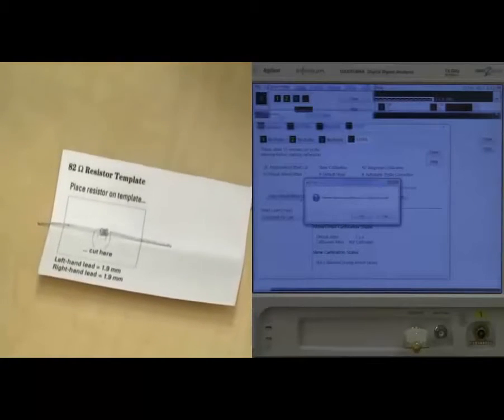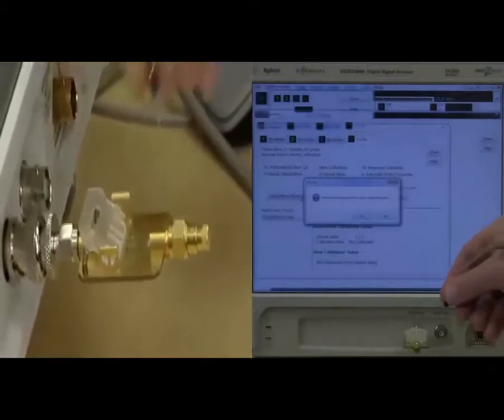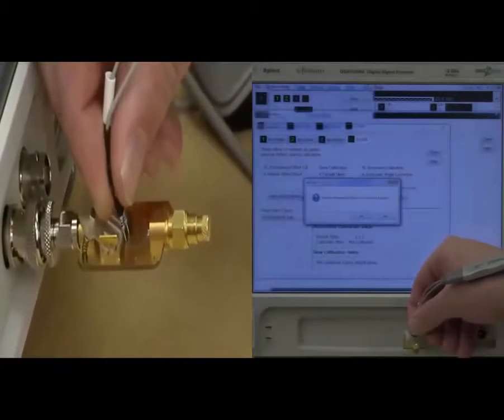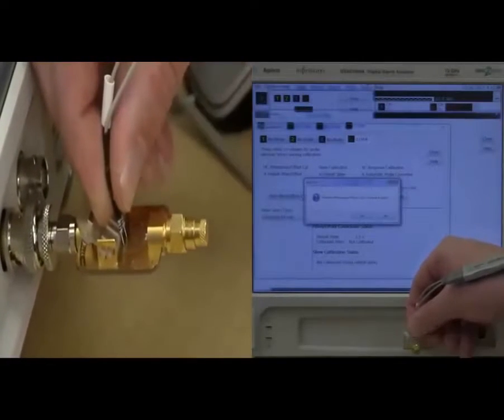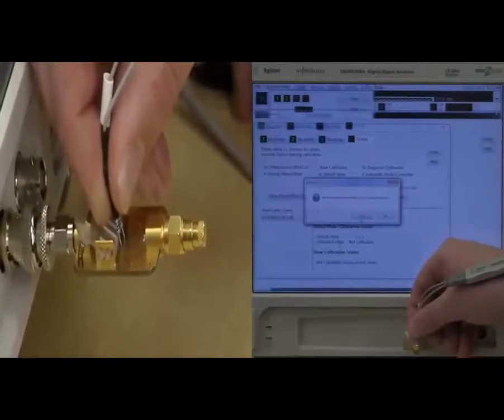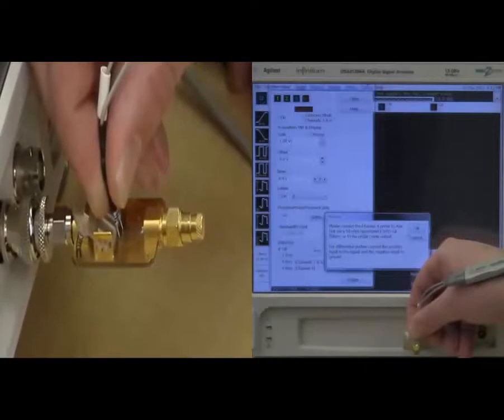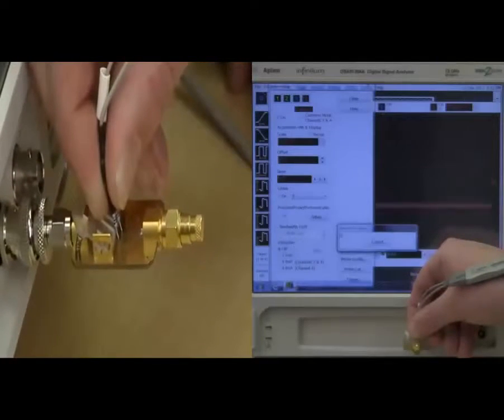It'll ask us if we want to do that, and of course we do, and we want to make sure that we put the plus side down to the center strip of the calibration fixture, at which point we can hit yes. And then it says to probe down to the calibration fixture, and I can simply hit OK.